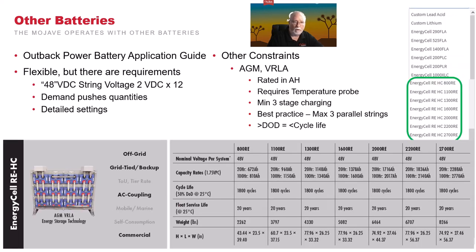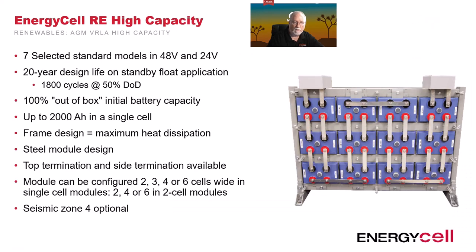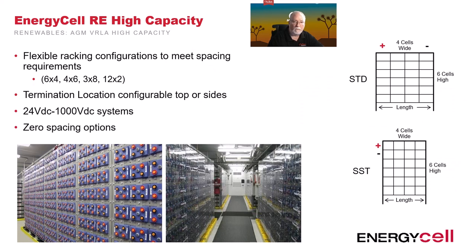Again, we also support our larger batteries, the RE high capacity. Again, there are 7 selected standards. What you're going to do, though, is you're only going to pick the 48-volt setups. There's a 20-year design life on these with 1,800 cycles at a 50% depth of discharge. 100% out-of-the-box initial capacity and up to 2,000 ampere hours per cell. These are very large battery cells that are strapped together. They can be configured in either 2, 3, 4, or 6 cells wide. So depending on the cabinet and the arrangement you need, you can rearrange them to fit in whatever application you need them to fit into. Again, they can be very large banks, anywhere from 12, 24, 48 volts DC up to 1,000 volts DC.